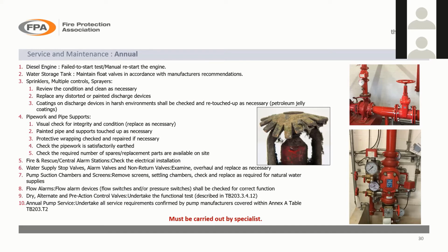So sprinkler heads, in the middle there, you can see a sprinkler which is damaged and dirty. Now, being dirty might not stop it from operating, but the research shows that it will inhibit it. It might well slow it down, and it might prevent it from operating, depending on what it's got coated with. In the event of this particular sprinkler operating, the deflector is damaged in any case, so the water spray discharge from it might not be very effective either. So sprinklers should be checked on a regular basis, at least on an annual basis, and any damaged or dirty heads should be cleaned or replaced, and that does require a specialist. That's not something you can carry out in-house.